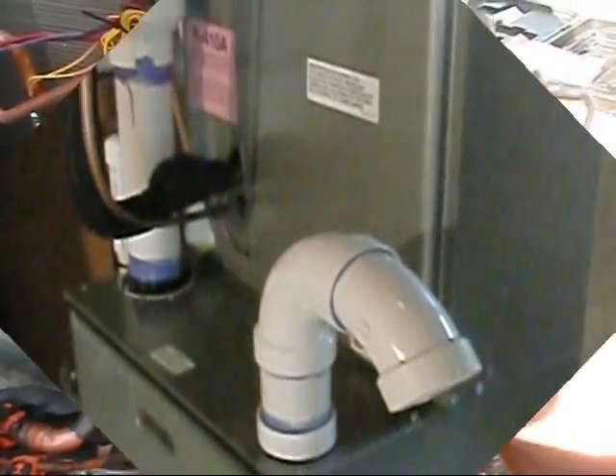I think we're looking good. I wanted to take care of what me and Dallas were talking about. Like I said, I like to go by the manual, and the manual requires that you have this three-quarter condensate line here. I'm going to take this off too, Dallas — static pressure. It requires that this be up right around the inducer. We'll try to get some footage of that too.